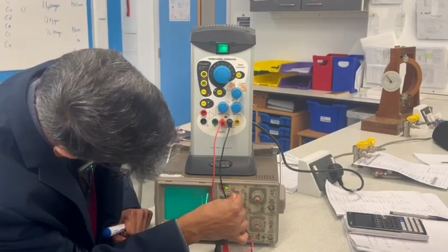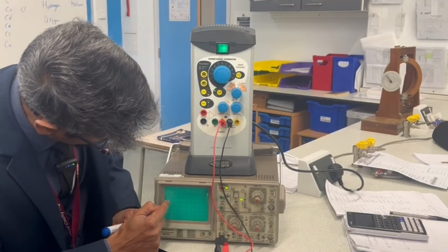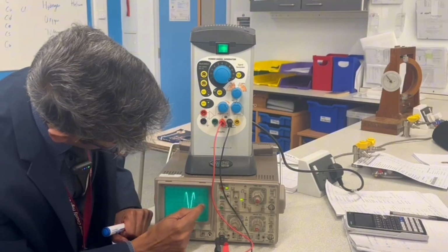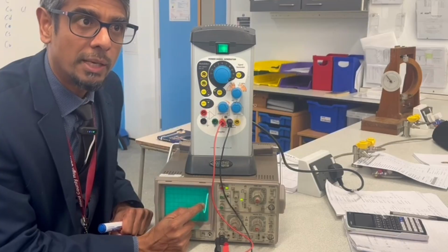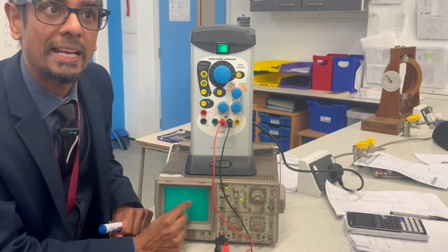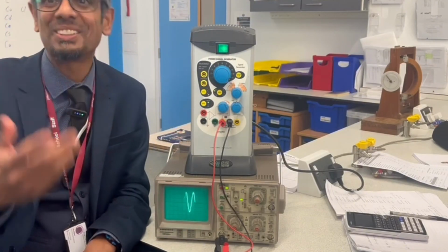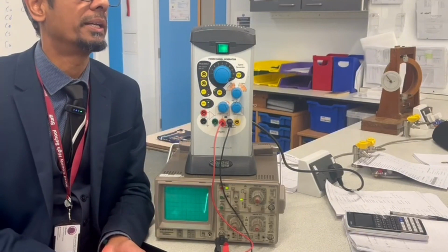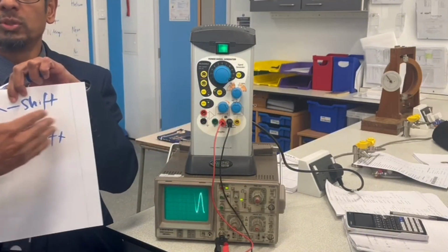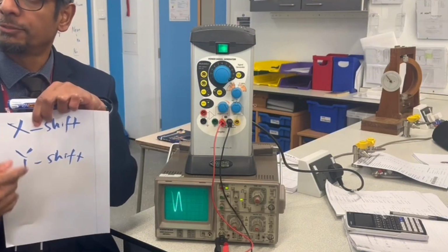So can you see what I'm doing now? I could start counting from here. So that's 1, 2, 3, 4, 5. And what am I going to count? Am I going to count here or am I going to count on that central x-axis? Why the central x-axis? Again, it's got higher resolution. That's it. That's what you need to know about it. So 2 things: X shift, Y shift. What do they do? Move your signal up and down, right and left.